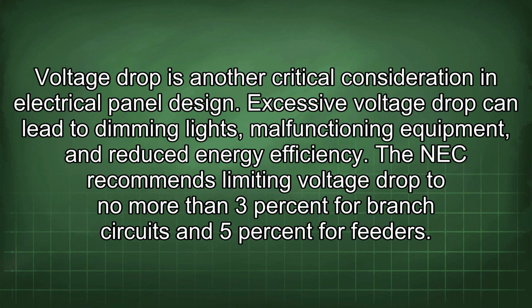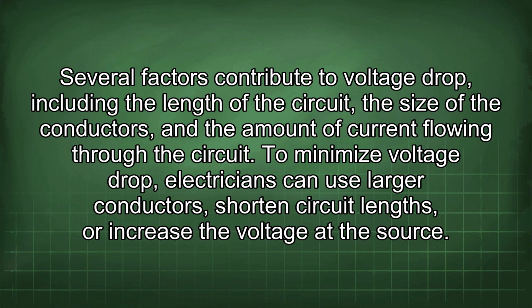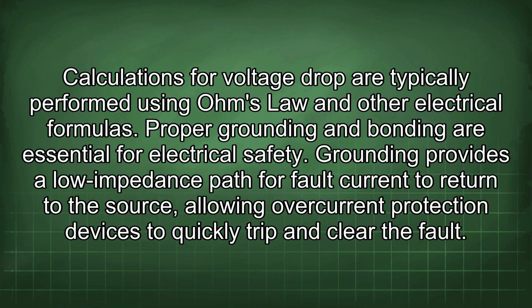Voltage drop is another critical consideration in electrical panel design. Excessive voltage drop can lead to dimming lights, malfunctioning equipment, and reduced energy efficiency. The NEC recommends limiting voltage drop to no more than 3% for branch circuits and 5% for feeders. Several factors contribute to voltage drop, including the length of the circuit, the size of the conductors, and the amount of current flowing through the circuit. To minimize voltage drop, electricians can use larger conductors, shorten circuit lengths, or increase the voltage at the source. Calculations for voltage drop are typically performed using Ohm's law and other electrical formulas.